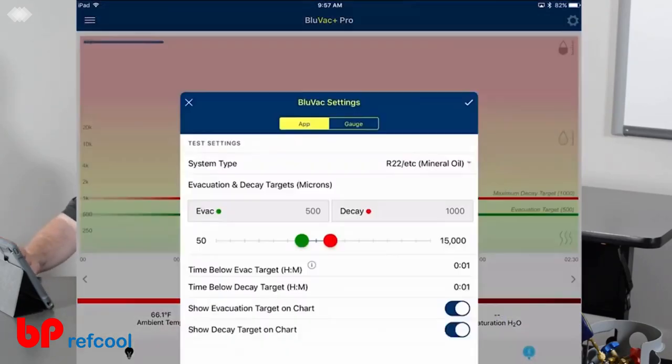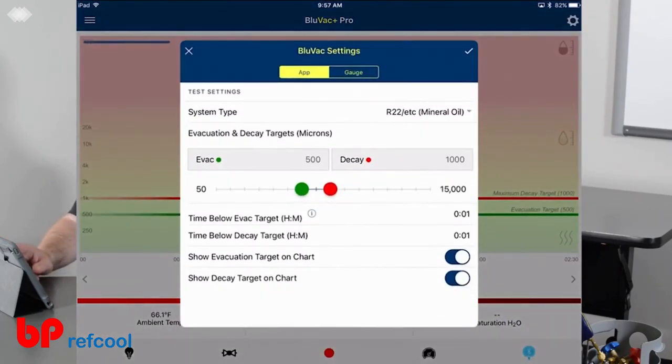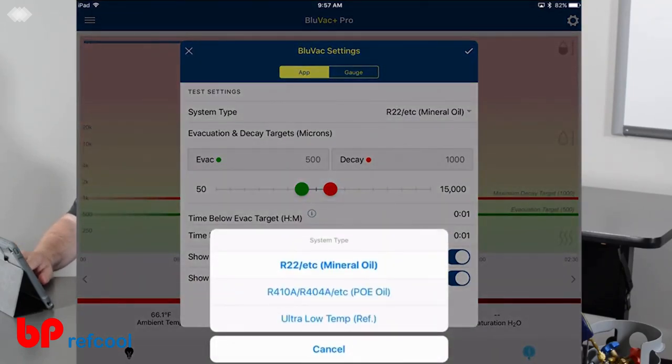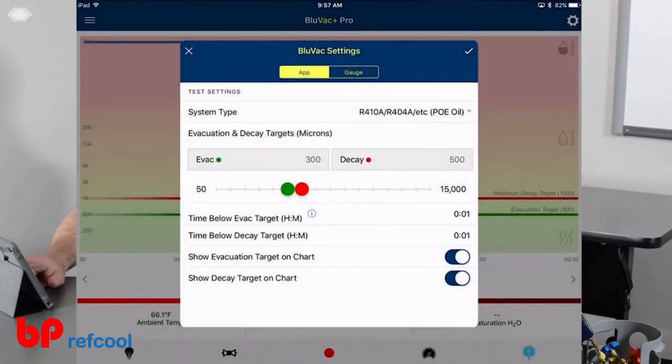I'm going to go ahead and tap the settings button for just a minute. You can see that we can select the type of system. These settings will change the depth and time of the vacuum. In this case here, if we select the POE oil, you can see it goes from 300 to 500.